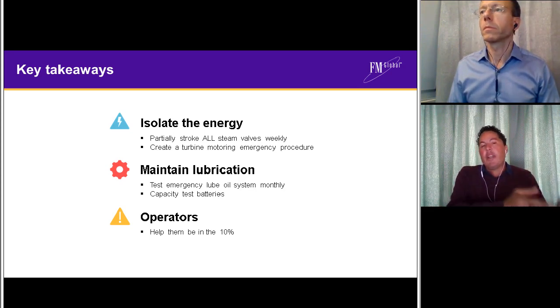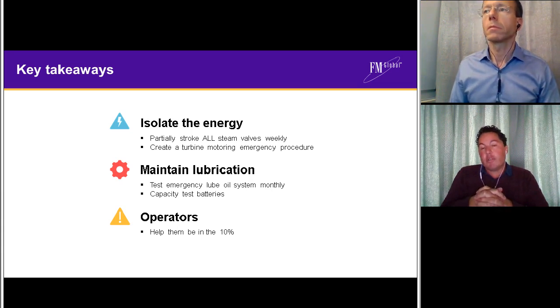And the speed probes are generally used for turbine control anyway, so you are generally pretty confident in the accuracy of that part of the system. And then you're testing the tripping system all the way up to the point where you're isolating energy. So no, you wouldn't have to physically overspeed it. That's one of the benefits of electronic systems, is that you don't have to induce the fault condition in order to test the protection.